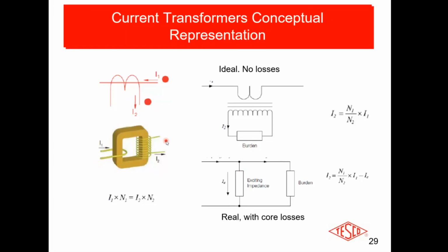Your transformers are always going to be under 100%. They're always 99.99 something because by design, they require an exciting impedance. So again, it's an important fundamental about transformers. They're always less than 100%.